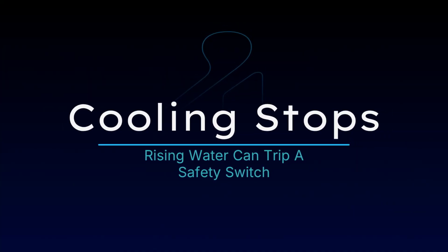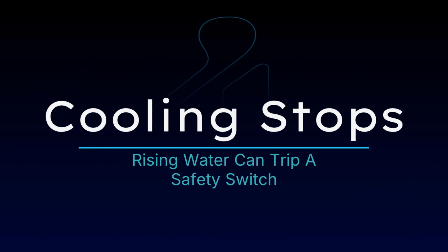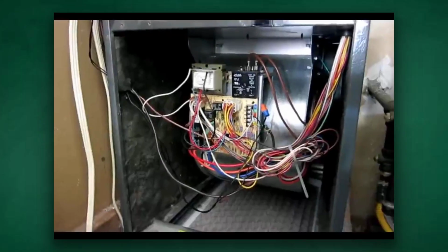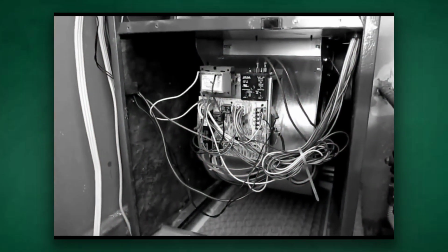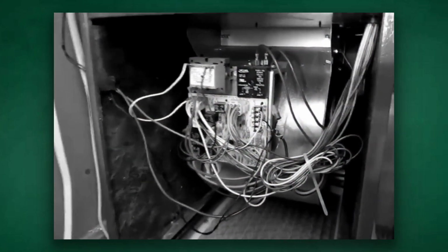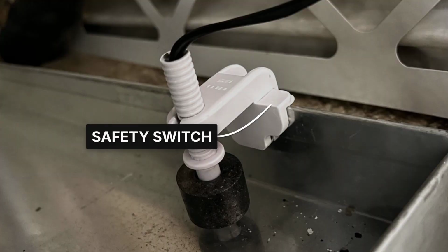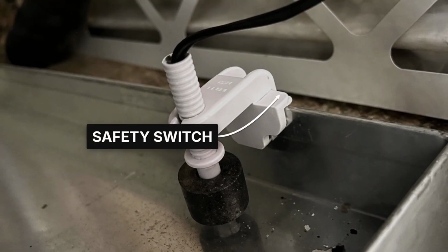The 4th claim begins with a house that suddenly stops cooling. The thermostat is on. The indoor unit is quiet, and because the failure appeared without warning, the homeowner assumes the most expensive component has failed. The small switch beside the drain pan may be doing exactly what it was installed to do.